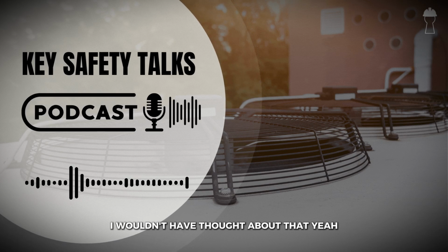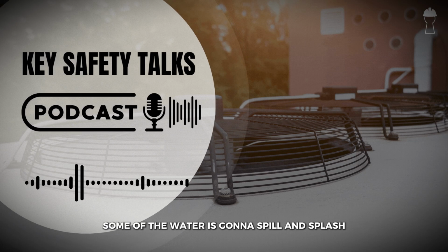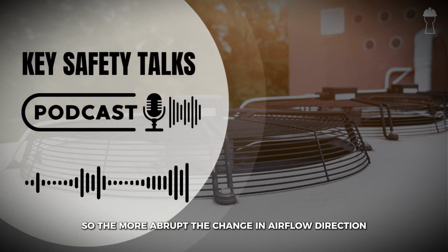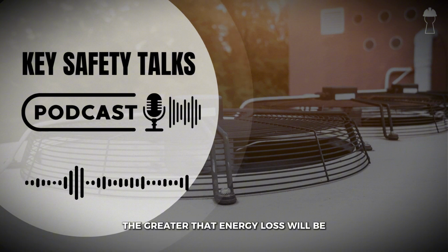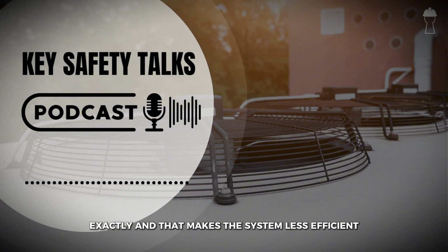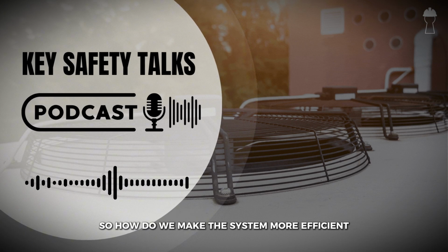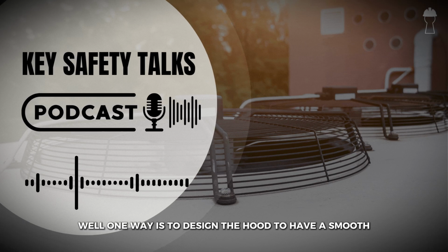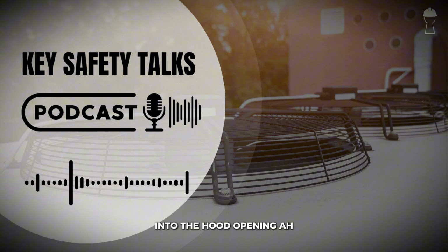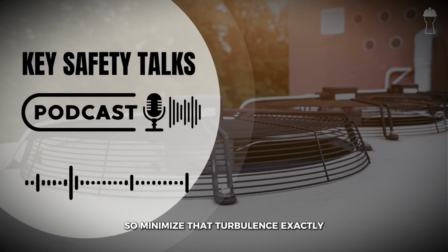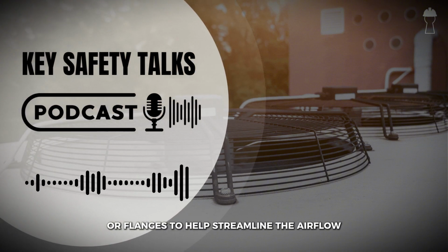I wouldn't have thought about that. Yeah, it's kind of like trying to pour water from a pitcher with a narrow spout. Some of the water is going to spill and splash because of that restricted flow. So the more abrupt the change in airflow direction and the smaller the hood opening, the greater that energy loss will be. Exactly. And that makes the system less efficient because the fan has to work harder to make up for that energy loss. So how do we make the system more efficient? Well, one way is to design the hood to have a smooth, gradual transition from the surrounding air into the hood opening. So minimize that turbulence. Exactly. Some hoods even have flared openings or flanges to help streamline the airflow.